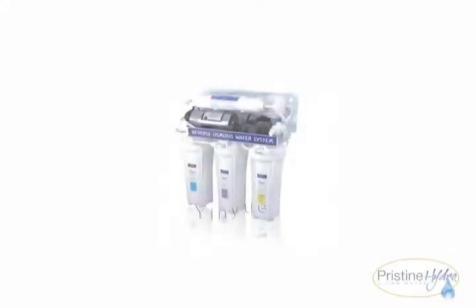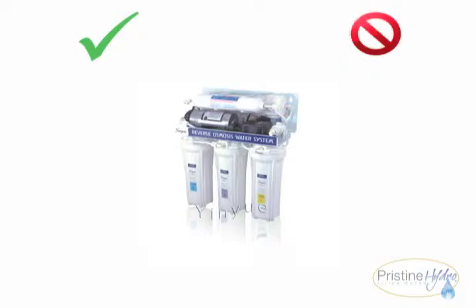A reverse osmosis system removes 90 to 99% of total dissolved solids, 99% of organics, 99% of pyrogens, and 99% of all bacteria. It does not remove sulfuric acid, nitric acid, perchlorate, chloramines, organic arsenic-3, or trivalent arsenic. Reverse osmosis systems do not produce appropriately mineralized alkaline water.